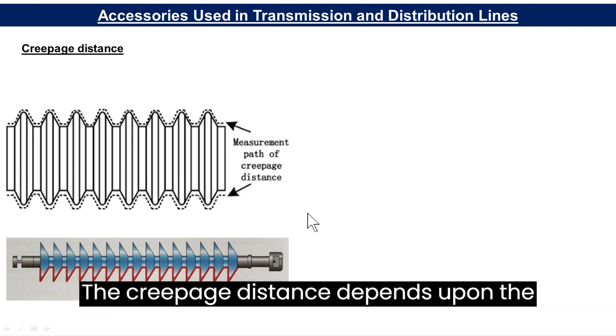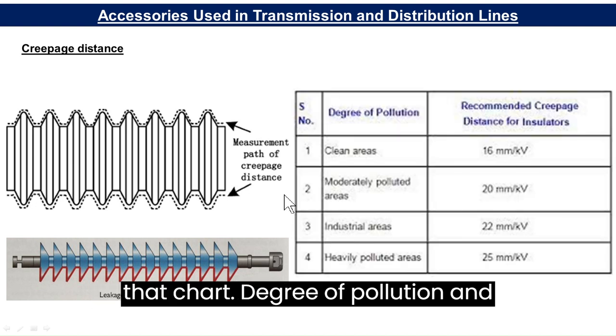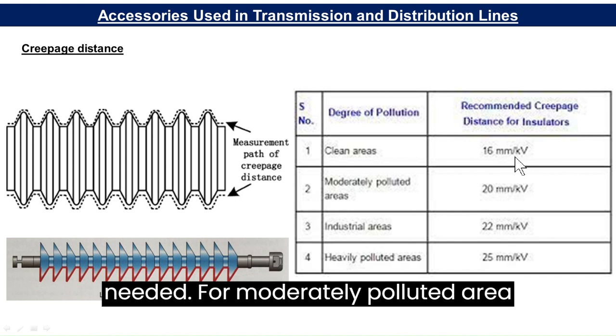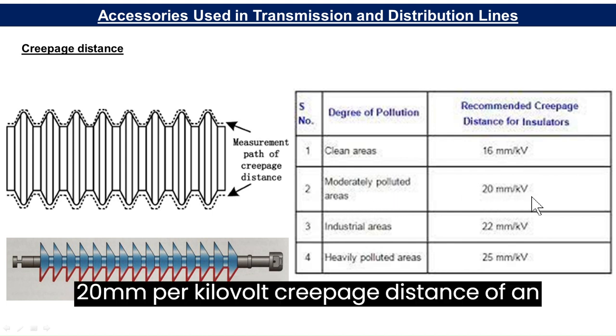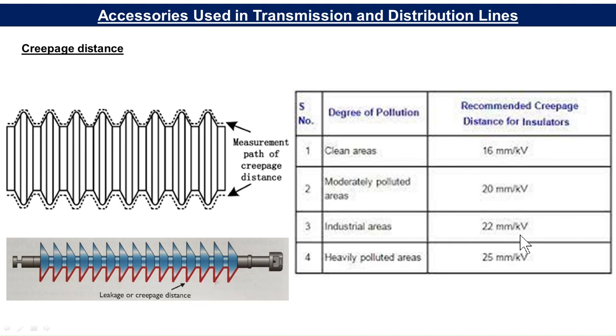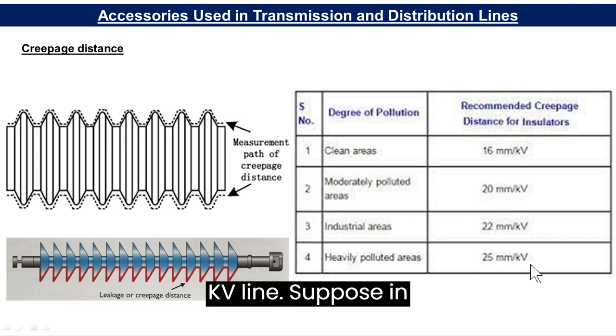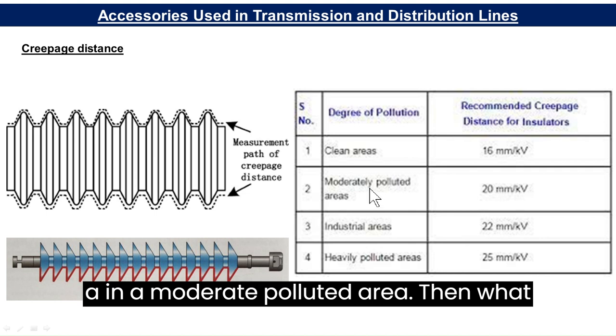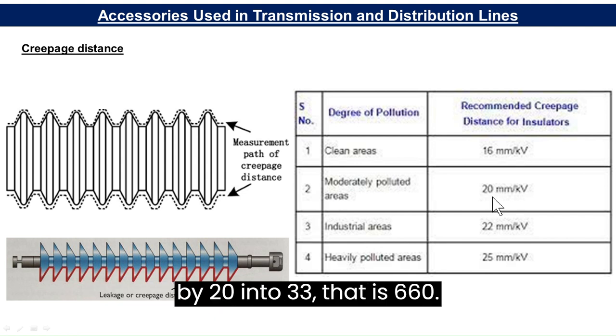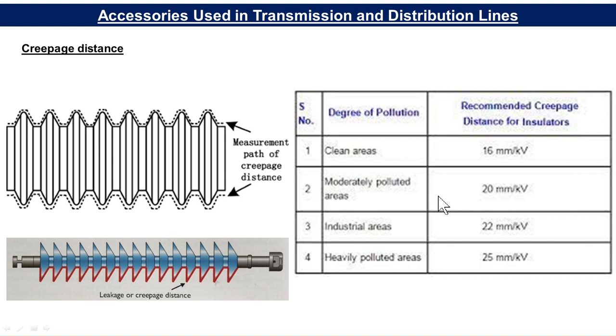The creepage distance depends upon the area's pollution level. For a clean area, 16 mm per kV is needed. For a moderately polluted area, 20 mm per kV is needed. For industrial areas with more pollution, 22 mm per kV is needed. For heavily polluted areas, 25 mm per kV is required. For example, for a 33 kV line in a moderately polluted area, the creepage distance is 20 × 33 = 660 mm.